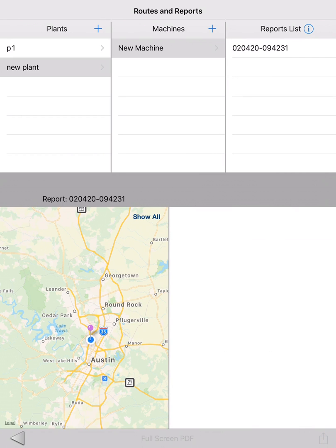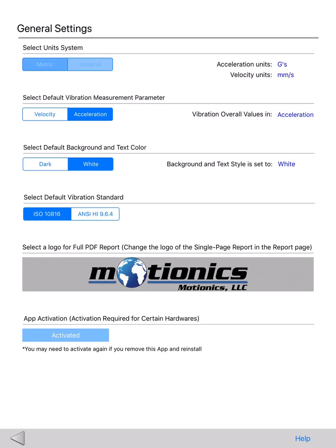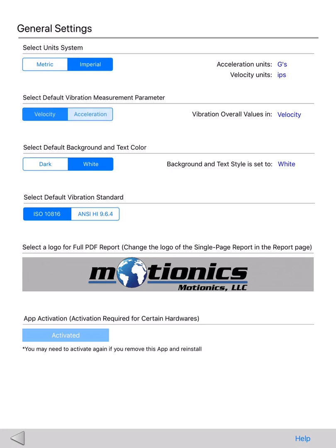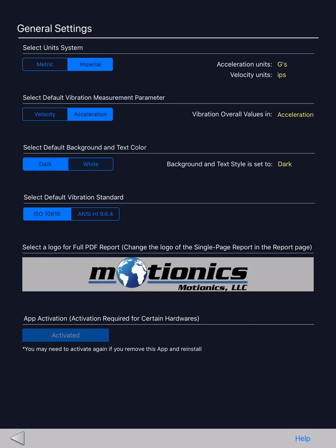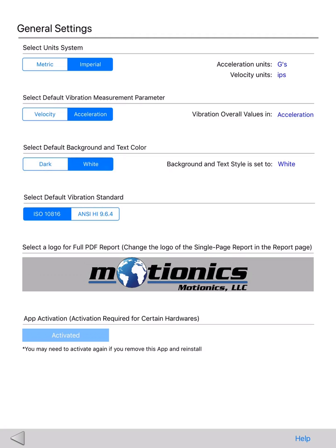Let's go back and take a look at the setting options in the app. Here, you can select to use metric or imperial units based on what you need. Default vibration measurement parameter can be set to velocity or acceleration, and this setting can also be changed during the test on the measurement page. You can select a dark or white theme for the app, and background and text color will adjust accordingly. Vibration test standard by default is ISO 10816, but the user can always customize. We have also implemented the ANSI HI 9.6.4 standard, specifically for pump tests.